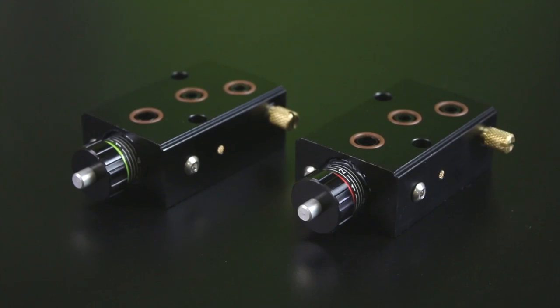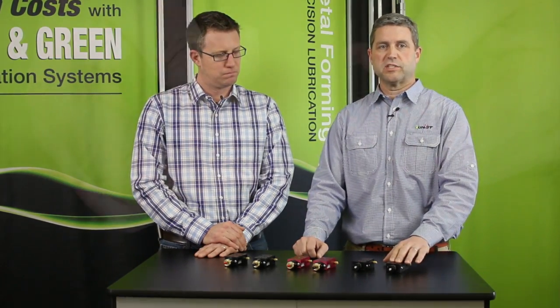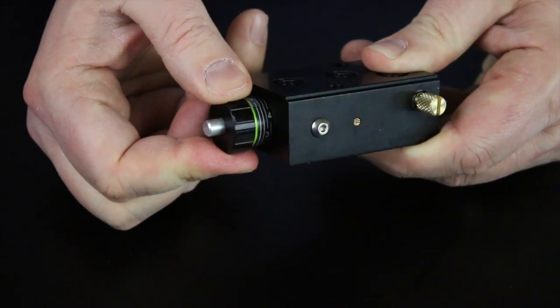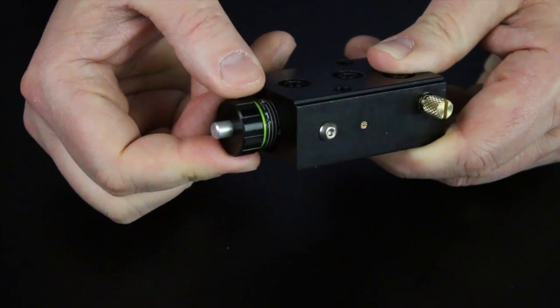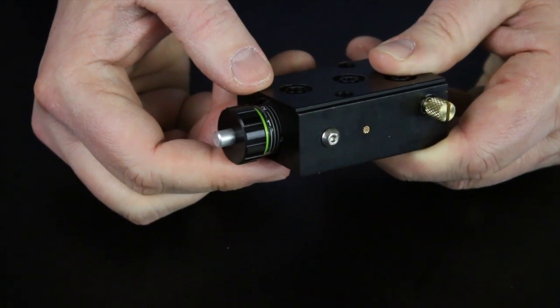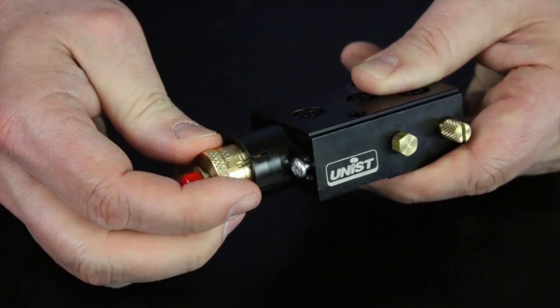The general operation concept and adjustability of the MV pump is the same as before. The new knob makes adjustment more precise with detents and easy-to-read markings. One noticeable difference: turning the knob clockwise decreases the pump output. This is the opposite of the standard pump and the red pump, so it is important to be aware of this.